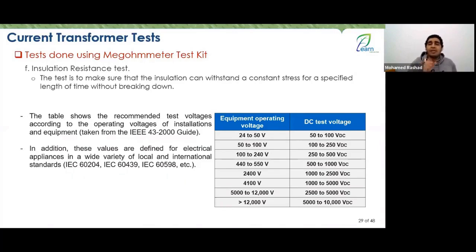I was honestly working at a station. I was in charge of testing protection, high voltage, and testing for GIS and so on. I was conducting a high voltage test at a 230 kV station with Aramco. In the very last second, while we were doing a high voltage test on the GIS, honestly, the insulation broke down. We could have stopped the test earlier, but you can't just stop. You have to keep going.